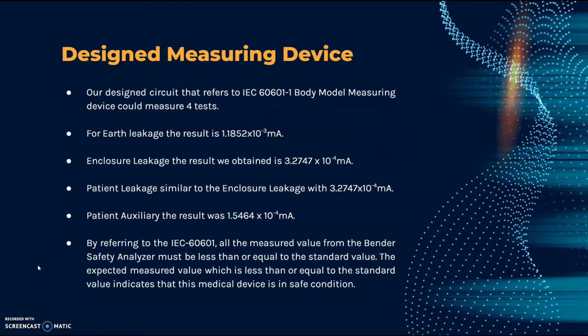For the device that we designed, it refers to the IEC 60601-1 body model. We were able to test 4 tests, which include earth leakage, enclosure leakage, patient leakage, and patient auxiliary. By referring to the IEC 60601, all the measured values from the Bender safety analyzer must be less than or equal to the standard value. If the measured value is less than or equal to the standard value, the medical device is in safe condition. That's all for the discussion.